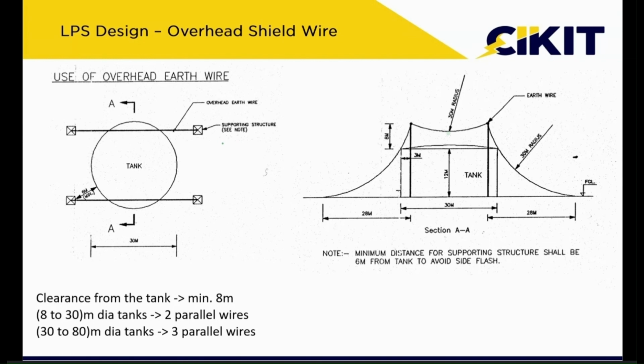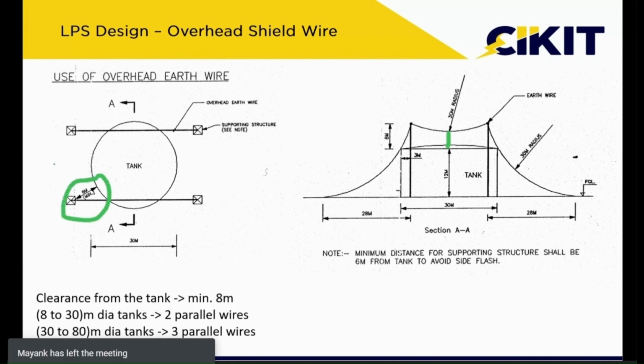And we need to ensure that the clearance is around 8 meters. From the top of the tank to the catenary wires and the rolling sphere, we have to maintain a clearance of around 8 meters. Here also we have to maintain the spacing to avoid flashovers between the tank and the lightning mast. By using this type of arrangement, we can ensure that all portions of the tanks are protected.